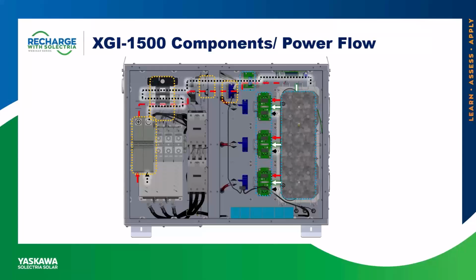So basically, starting with troubleshooting procedures, if you arrive on site, your inverter is completely off, you have other units on site that are producing just fine in full sun, and the unit is completely dead, first, obviously, check to see if there's any DC voltage present. Maybe the combiner was turned off or anything like that.